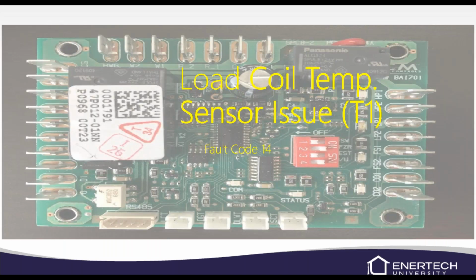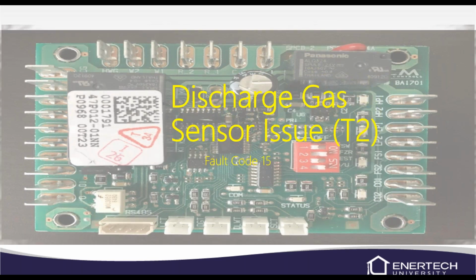Sensor issues, we do have quite a few different faults, and I'm not going to get too in depth with the faults. I don't expect you to remember all the faults, but they are listed in the manual. So like a load coil temperature sensor fault would be a T1 fault, and that would be a code 14 in the manual or on the diagnostic chart. These are just some of the sensor issues. Discharge gas temperature sensor issues, code 15. So it'll tell you if the sensors are having issues as well as a discharge fault.